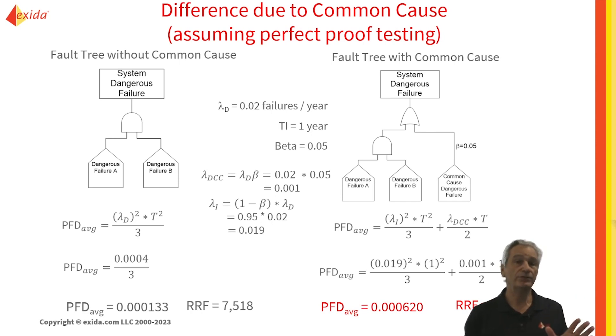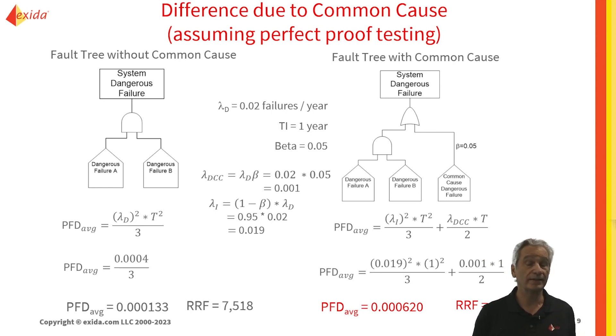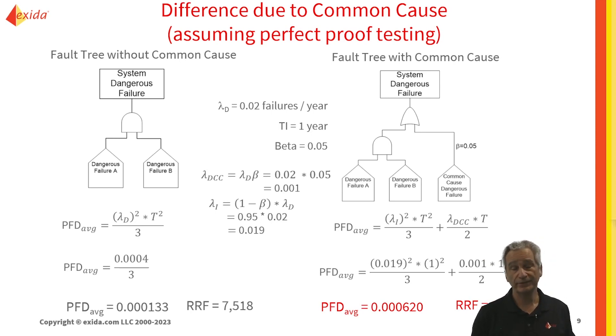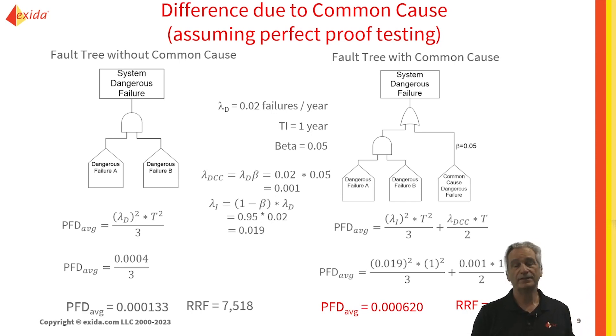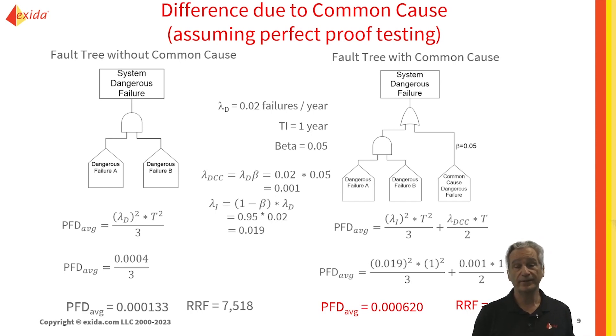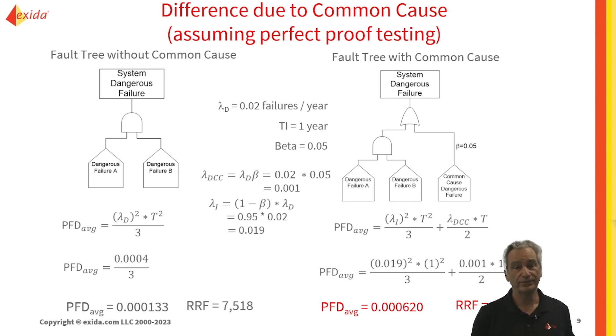So that's why we cannot ignore common cause. If you choose to ignore common cause in your SIF design where you've got redundant elements, all you're doing is fooling yourself into thinking you're going to get a much more reliable system than you actually have. We do need to consider common cause. The standard also requires us to document reasons for not including common cause if we have a redundant system.